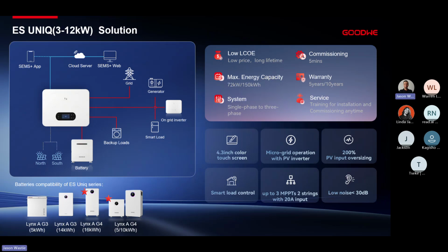On the bigger side of the inverters, on the 10 and 12 kilowatt units, we have got 2 MPPTs and 2 strings each. In parallel, up to 6 of these units, making a maximum of 72 kilowatts and then 150 kilowatt hours. Same kind of solution, single phase to 3-phase, we can do on these units as well.